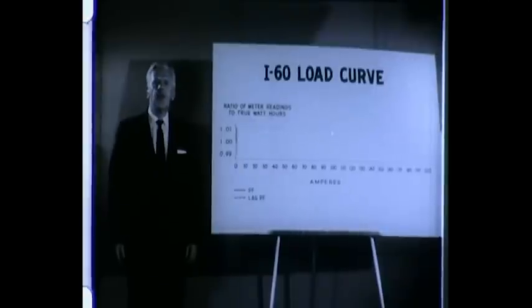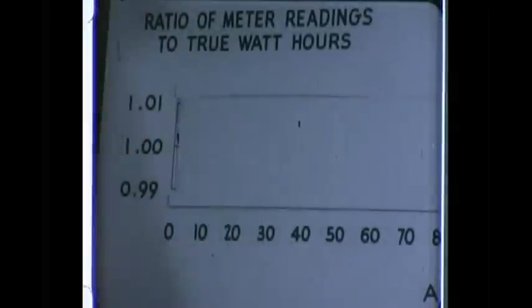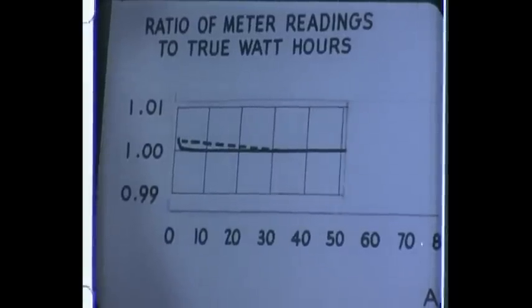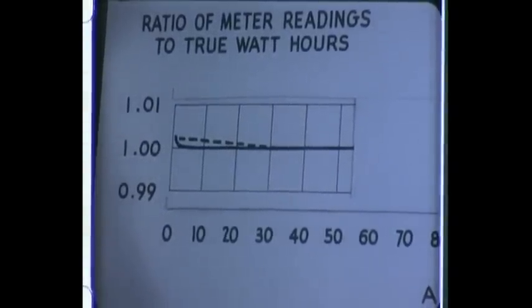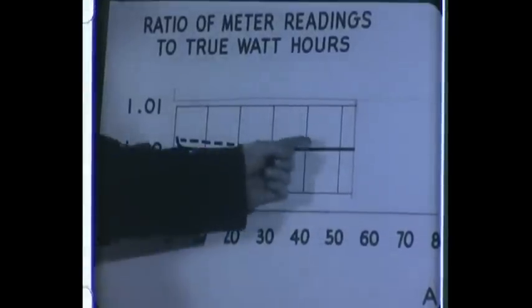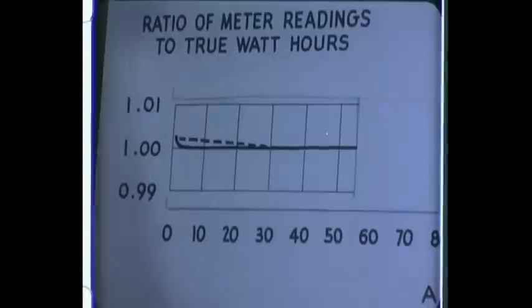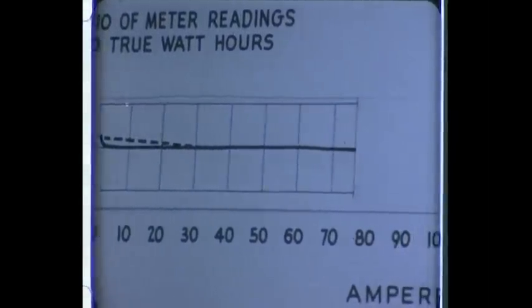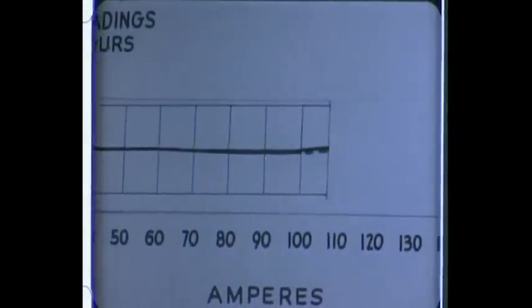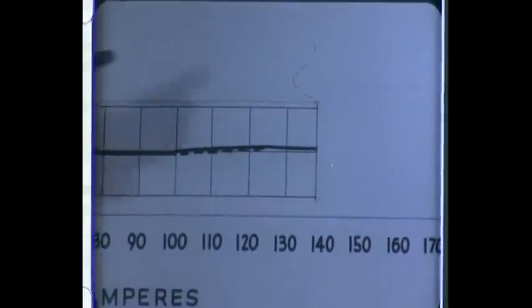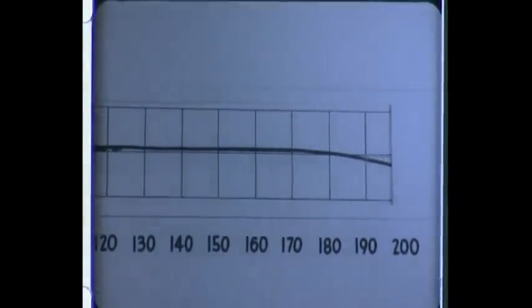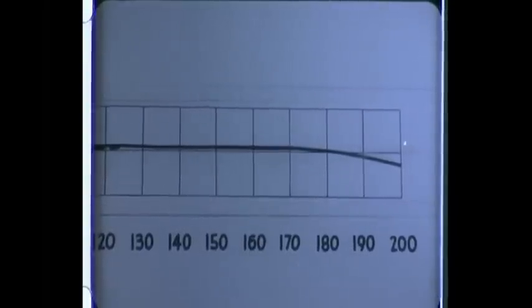In the past, new meter designs have placed the major emphasis on extending the overload range from 200% to 400%, and finally to 666 2/3%. On the I-60, the range has been extended to 666 2/3%, but a very substantial portion of the design effort has been on the light load end of the curve. Here at the first 50 amperes of the load curve, the I-60 is right on. It is right on not only at the full and light load test currents of 30 and 3 amperes, but also at 15 amperes, and it is within 0.2% or better at 1.5 amperes. At the heavy load end of the curve, the meter rises to only 0.5% error at 150 amperes, and at a full 200 amperes drops off only 0.75%.